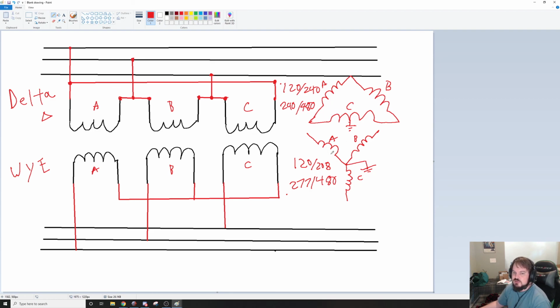But if you need a neutral, like with a Y, you can't have normal voltage. You can't have 240 volts with a neutral with a Y system. If you need 240 volts, say you have some sort of three-phase system that needs 120/240, then you're going to have to go with a center tapped delta. That means if you read from here to here, you're going to have a high leg because you're going through 1.5 coils, versus if you read from here to here, you would get 120. If you read across that coil, you'd get 120. If you read across C, you'd get 120.